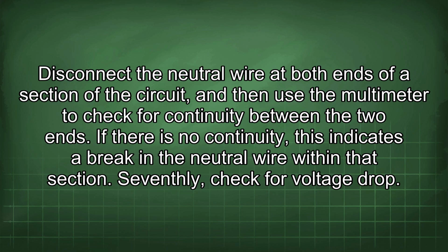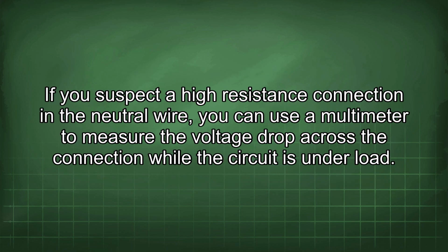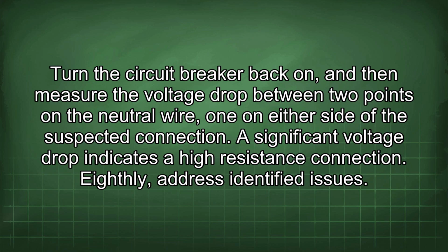Seventhly, check for voltage drop. If you suspect a high resistance connection in the neutral wire, you can use a multimeter to measure the voltage drop across the connection while the circuit is under load. Turn this circuit breaker back on and then measure the voltage drop between 2 points on the neutral wire, one on either side of the suspected connection. A significant voltage drop indicates a high resistance connection.